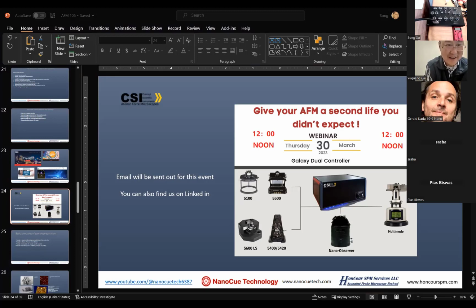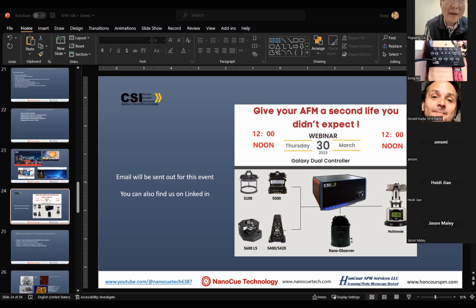Steve, do you have a comment? Well, they definitely should not be different. If there's a deviation between what you're seeing on the software and what you're seeing on the hardware, it's typically indicative of a problem with your system. I would need a little more information to understand how much of a difference you're seeing. We have two AFMs. One AFM differs a little bit, roughly 0.3 volts to 0.5 volts in deflection. On another AFM, the difference is always about 5 times.